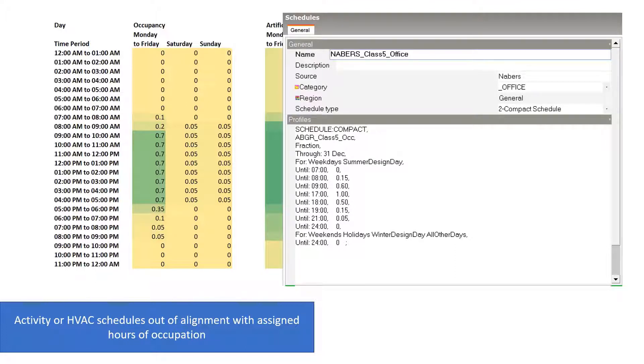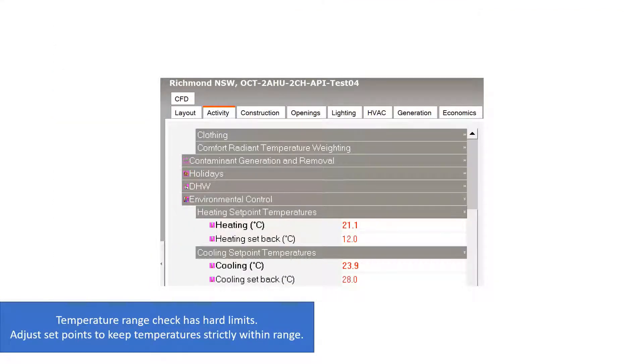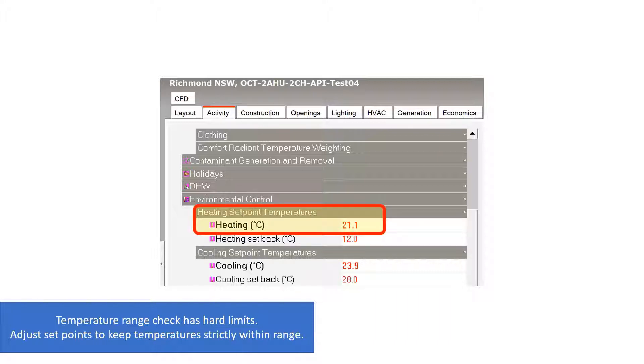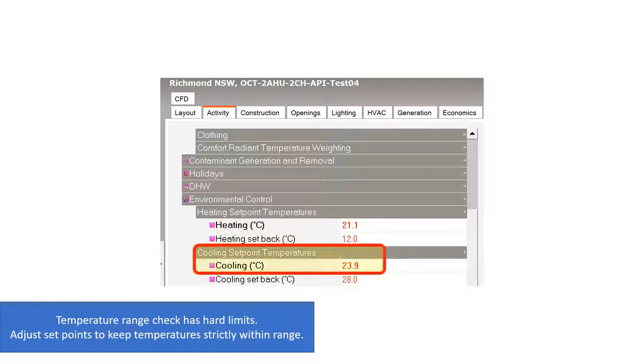Also note that the temperature target range has hard limits. A zone temperature of 24.01 degrees, for example, will be counted as out of range if the upper limit of the target temperature range is 24 degrees. It may be necessary to alter the environmental control set points slightly so that the zone temperature stays completely within the target range during occupied hours.